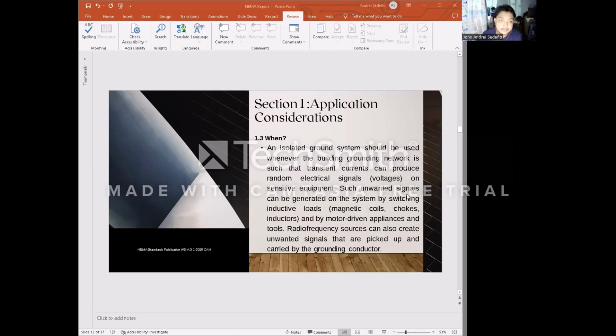Next is when. An isolated ground system should be used whenever the building grounding network is such that transient currents can produce random electrical signals on the sensitive equipment, such as unwanted signals generated on the system by switching inductive loads, magnetic coils, chokes, inductors, and by motor-driven appliances and tools. Radio frequency sources can also create unwanted signals that are picked up and carried by the ground conductor.